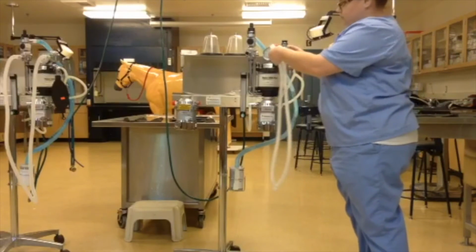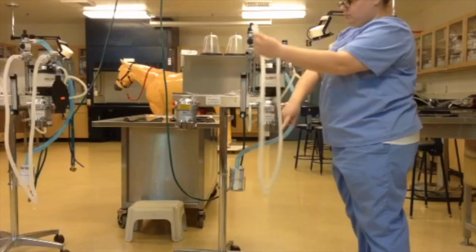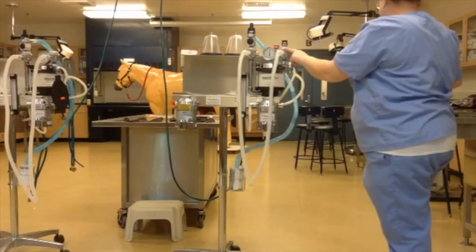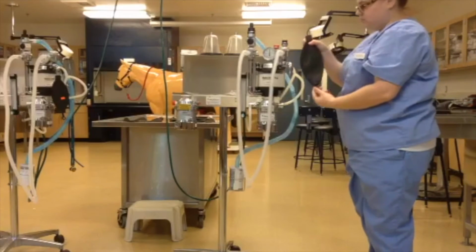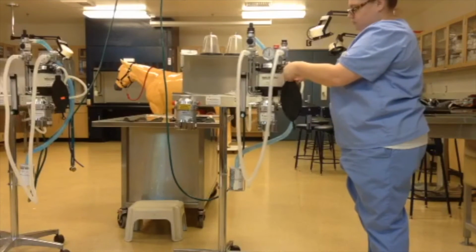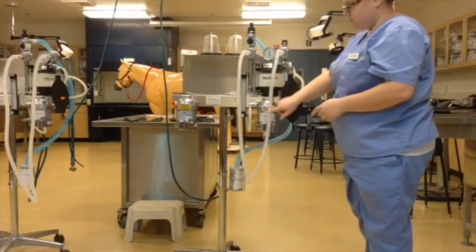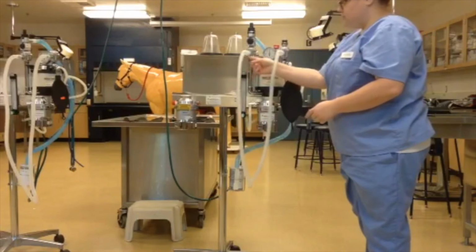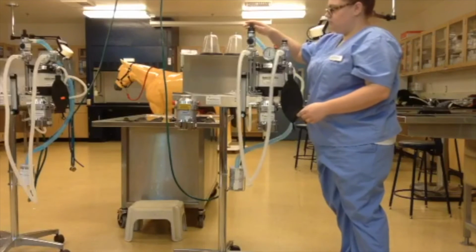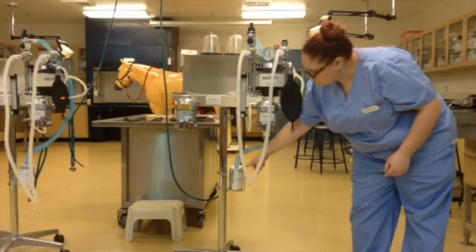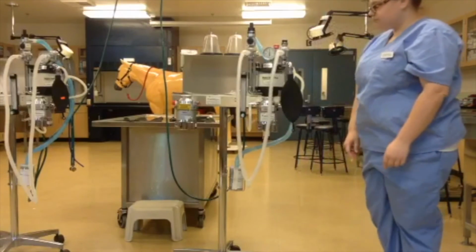Now I'm connecting the inhalation tube, which connects to the inhalation unidirectional valve, and the exhalation tube to the unidirectional exhalation valve. Now the reservoir bag is being connected. There will be a flow of oxygen and anesthetics in the inhalation tube and carbon dioxide and anesthetics through the exhalation tube. Now oxygen, carbon dioxide, and the anesthetics will flow through the pop-off valve to the scavenging system.